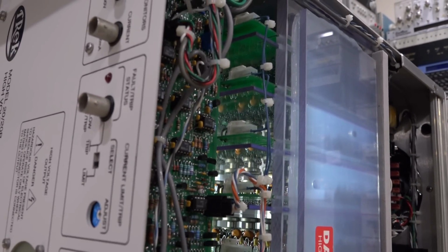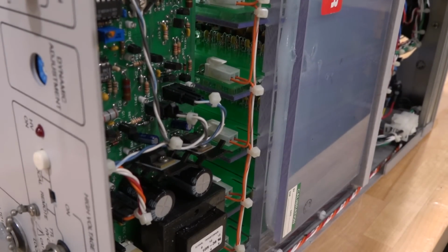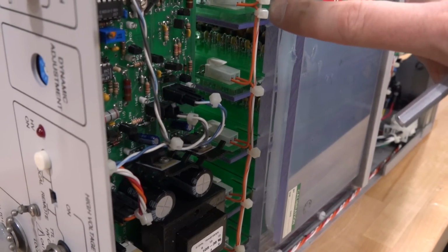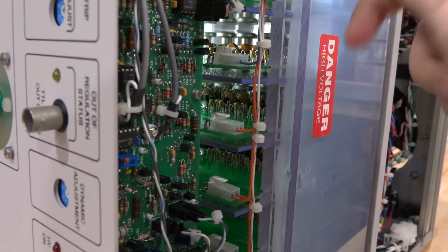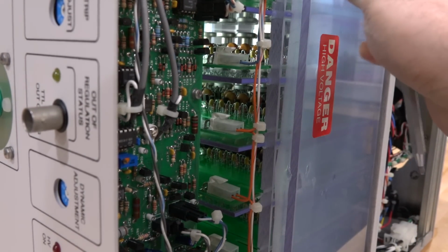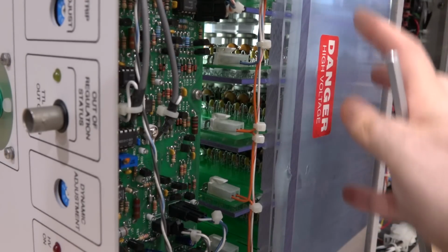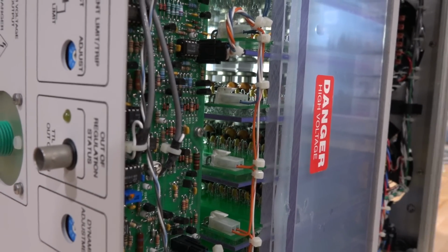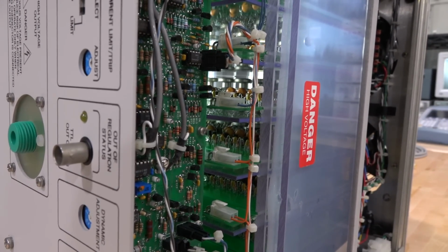But yeah, it's an amazing thing that somebody said, you know what, that's how we're going to put this thing together. It must have been a crazy proposal at a time when this was initially conceived. Now look at these plexiglass layers. They're all glued together, multiple layers of them, because on the other side we have such a high voltage. Unfortunately, this cannot be taken off very easily. It looks like they assembled this whole thing and they push it into the unit. And I don't want to take it out because it's going to be very hard to put it back together, and it's a risky instrument to play around with anyway.